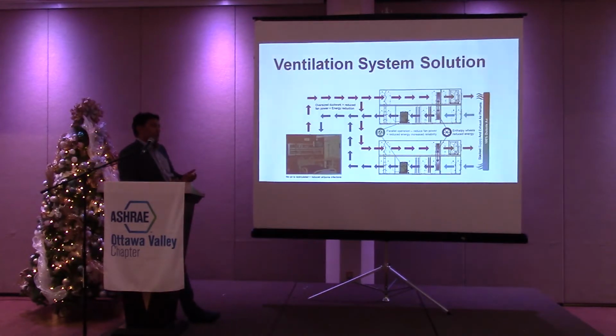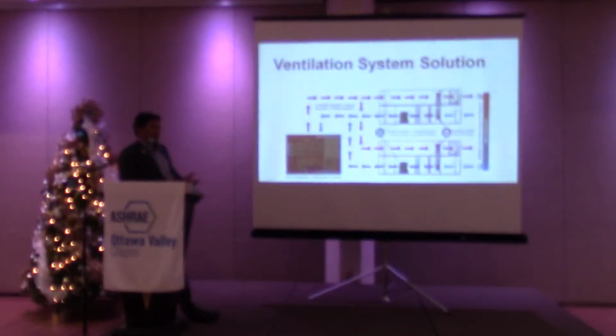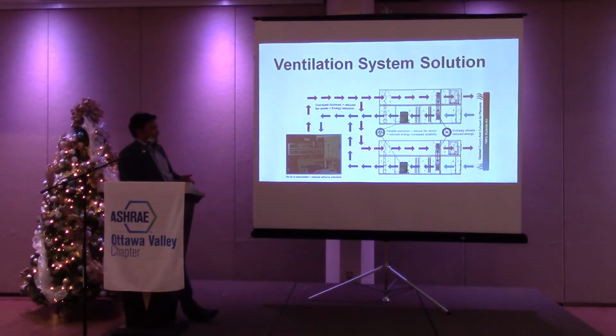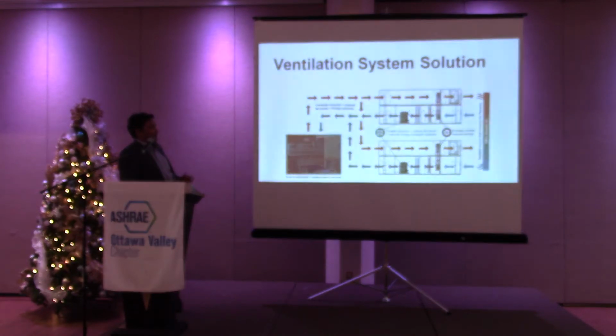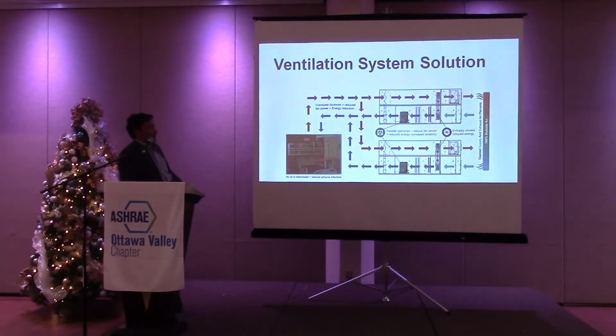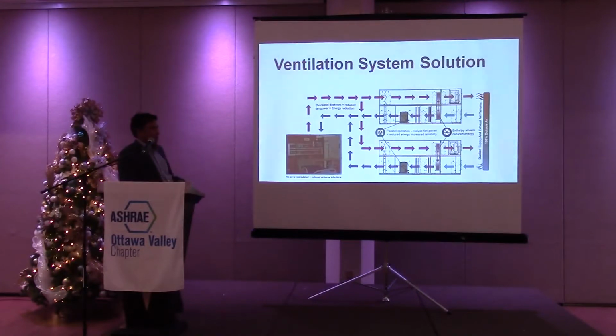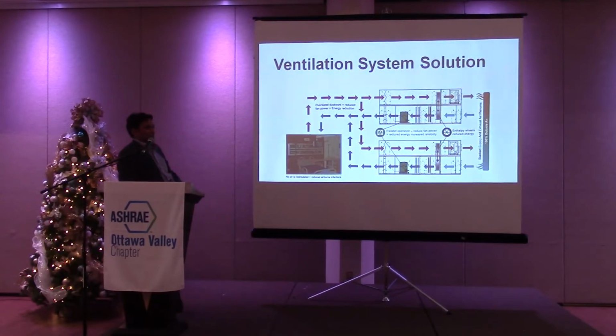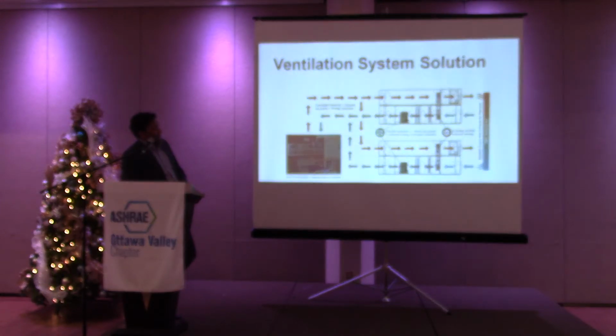Right? So we distinguish between what we call non-breathable exhaust and breathable exhaust. So something like a fume hood, biosafety cabinets, welding hood, we'd be using glycol runaround coils. Any other spaces in the facility where you had the opportunity to breathe the air on the way to that exhaust hole, like you would in a washroom, we figured it's safe. But safe from a standpoint it might smell, but it's not gonna kill you. So we looked at that and said that's breathable exhaust, and so we used enthalpy recovery wheels throughout the facility to improve energy efficiency.